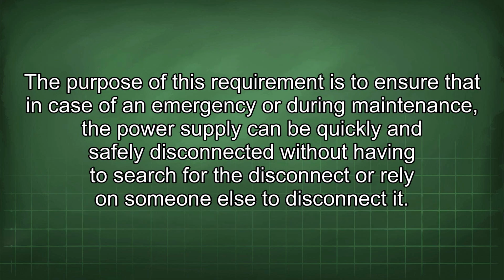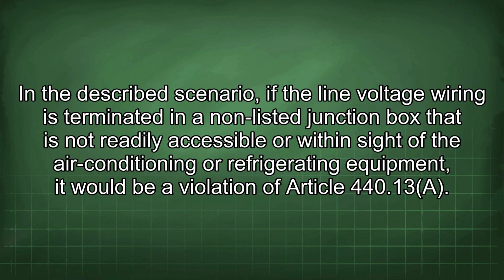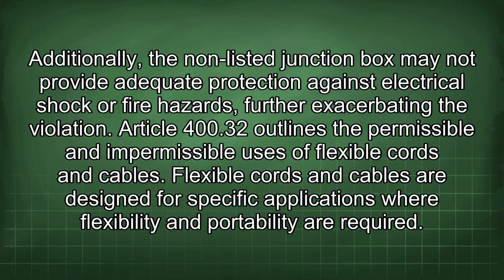The purpose of this requirement is to ensure that in case of an emergency or during maintenance, the power supply can be quickly and safely disconnected without having to search for the disconnect or rely on someone else to disconnect it. In the described scenario, if the line voltage wiring is terminated in a non-listed junction box that is not readily accessible or within sight of the air conditioning or refrigerating equipment, it would be a violation of Article 440.13(A). Additionally, the non-listed junction box may not provide adequate protection against electrical shock or fire hazards, further exacerbating the violation.